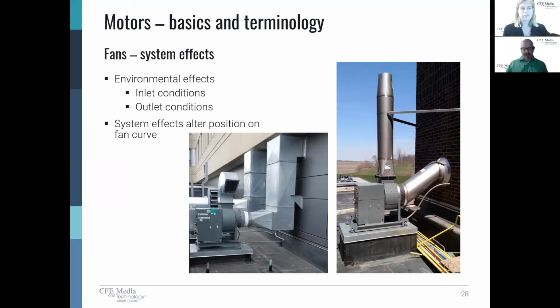And this matters because as you change your inlet and outlet conditions of your fan, or you change your duct, you generate system effects. These are problems, not necessarily problems, but they're restrictions from the ideal. So as we generate system effects, we're going to change where we live on that fan curve. I can tell you the image on the left, that fan was not able to generate enough airflow because of the system effects and the offset in the ducts to actually be able to meet balance requirements.